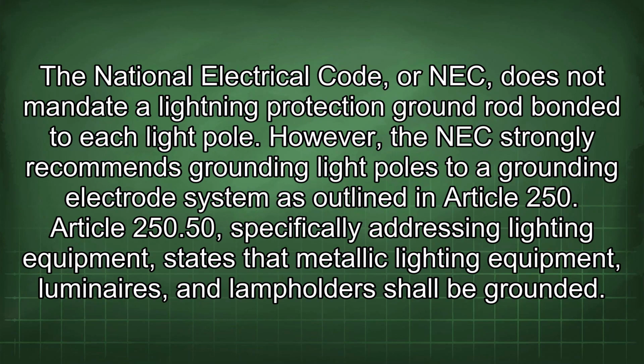The National Electrical Code, or NEC, does not mandate a lightning protection ground rod bonded to each light pole. However, the NEC strongly recommends grounding light poles to a grounding electrode system as outlined in Article 250. Article 250.50, specifically addressing lighting equipment, states that metallic lighting equipment, luminaires, and lamp holders shall be grounded.